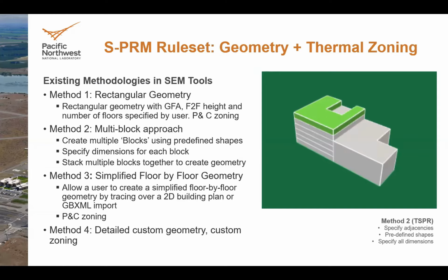This scale - what we've observed from a LEED perspective, I think this will be a little less under 90.1 2016 - is that changes in system types between the baseline and proposed can have a substantial effect based on differences in zoning, particularly because of the 90.1 2016 baseline rule set. So appropriate perimeter-core zoning, and maybe even dual core zoning to account for significantly different space types in the core, would be important for the baseline versus proposed case.